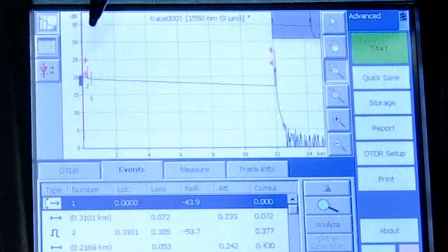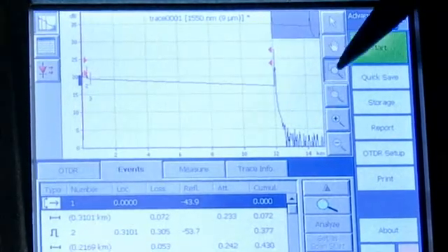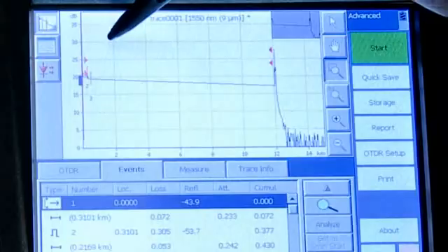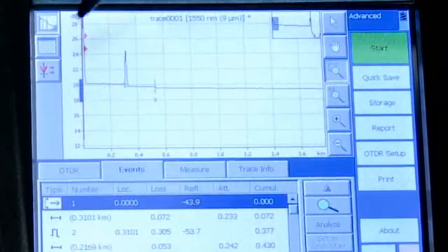After the preset acquisition time has expired I can see that my trace is about 13 kilometers long and most of the events are concentrated around the beginning and I will zoom in there. There are two events, number two and number three.